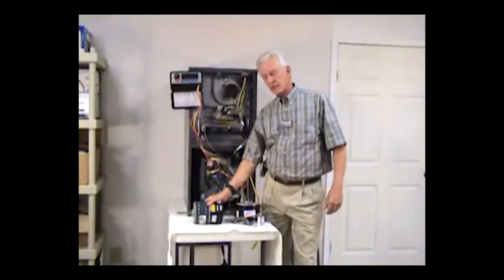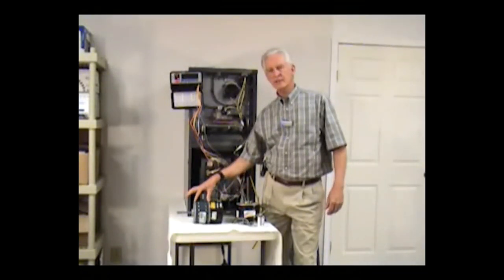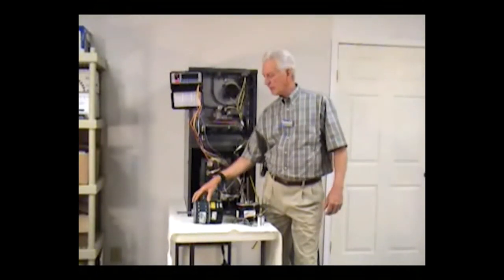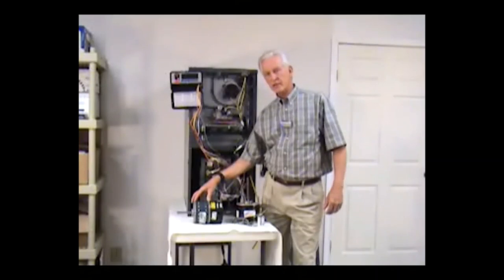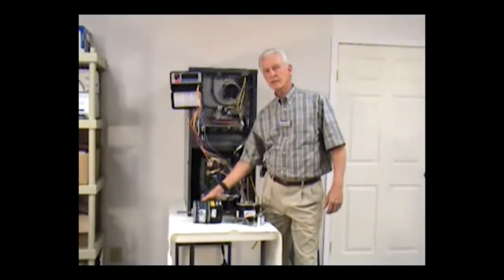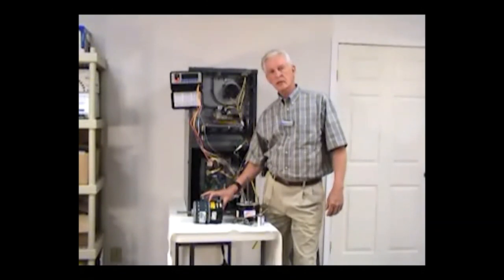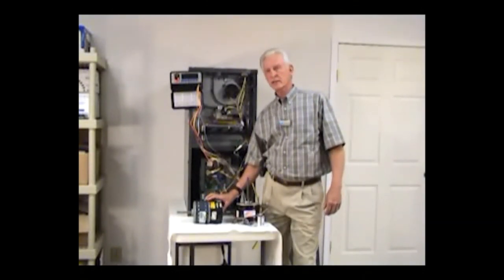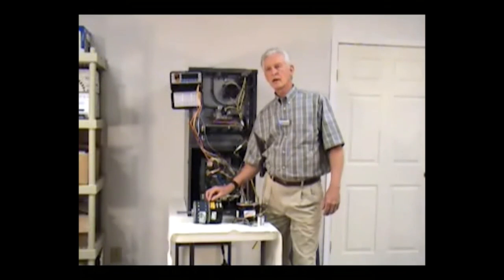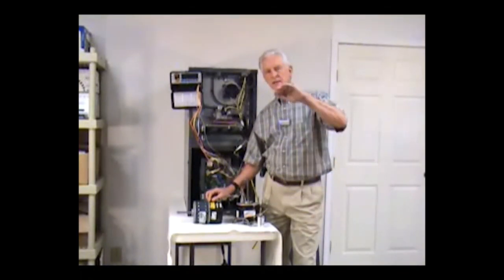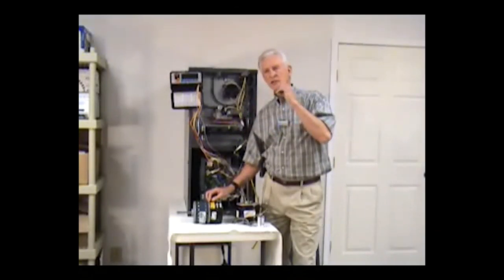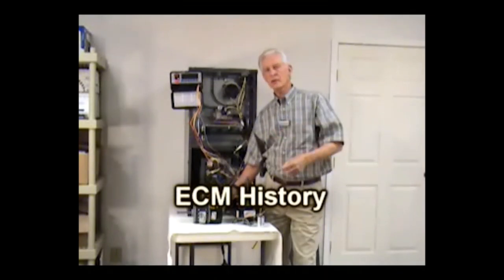Let's go back and look at the actual motor itself, and there may be some confusion out there as far as the mentioning of the fact that this is an AC-DC current motor, three-phase, and the stator in this motor, or the winding section of this motor itself, is a three-phase AC winding itself. Okay, so our module is going to take your 115 to 230 volts and convert it to a DC current, and then also take the DC current and convert it to an AC current that is supplied to the motor at three-phase. And the sine wave that we have there determines what RPM that motor is going to turn at that point.